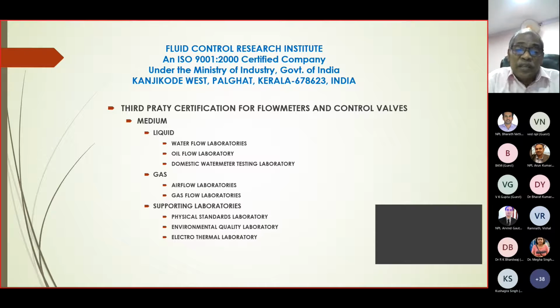Of course, we have supporting laboratories also, like the physical standards lab, where we can keep the reference standards and get them calibrated and make them traceable to national and international standards. The other one is the environmental quality laboratory, where we can do the calibration of noise and vibration. Shakers are there. You can calibrate accelerometers, hydrophones, etc. Then lastly, the electrothermal laboratory, where we can calibrate electrical parameters like voltage, current, and also thermal parameters. We have temperature baths, chambers, thermometers, etc. We can calibrate RTDs.